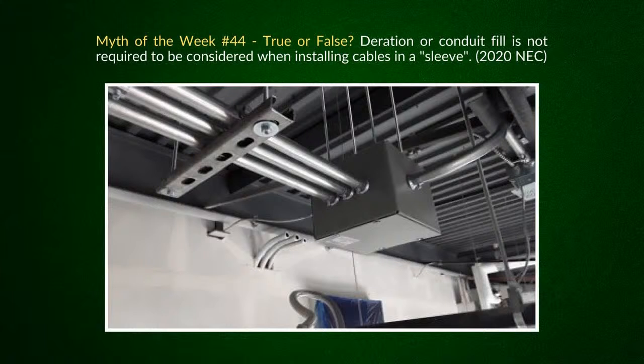This is something I had a question about, and you brought it up too. I don't remember ever doing an adjustment correction on those cables. Most of the time we're oversizing those raceway sleeves to fit as many cables as possible, but a lot of times it's discrete wiring without much ampacity, maybe a 2-amp cable with 20 of them in there. Typically you're just using that sleeve to protect the cable from damage as it transitions out to the tray, and from there it goes out to whatever device is in the field.